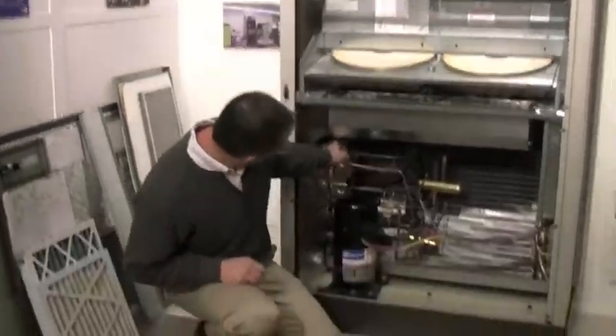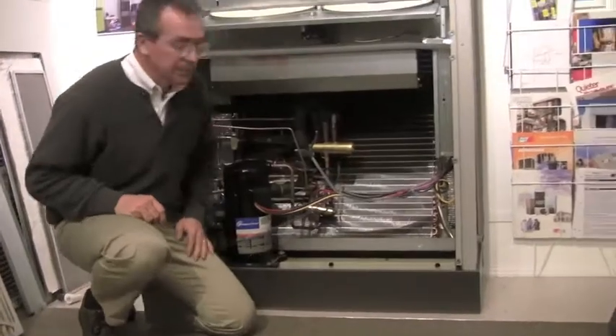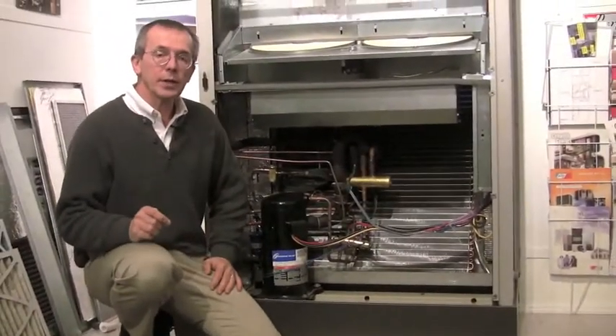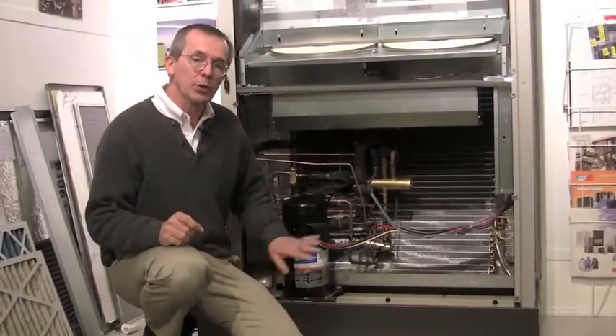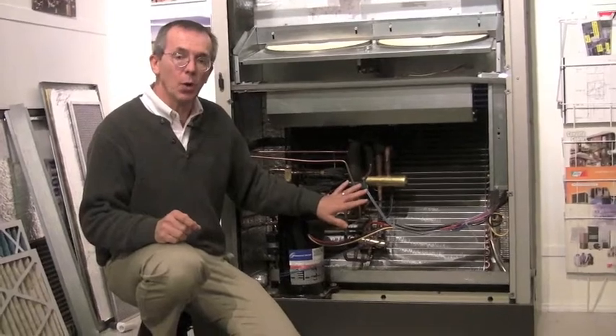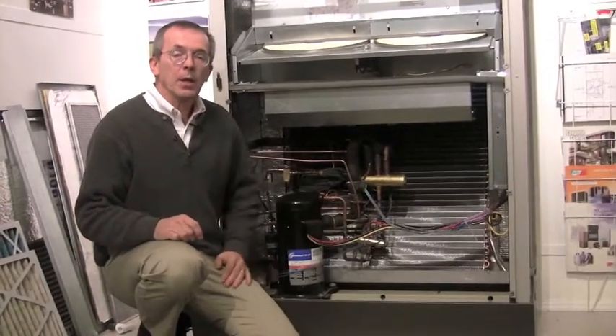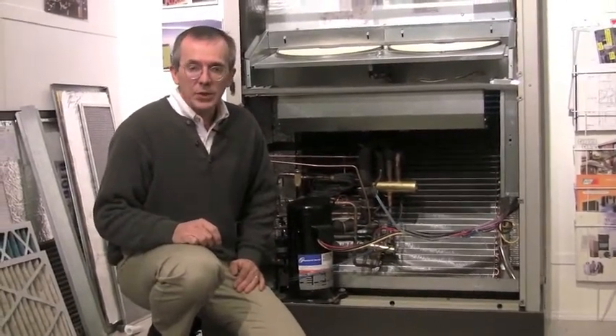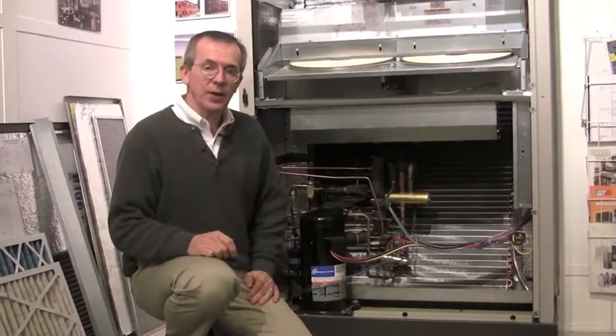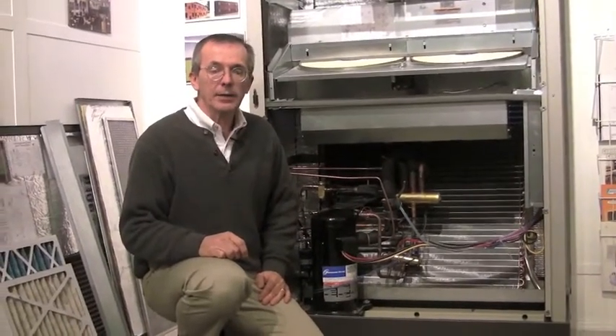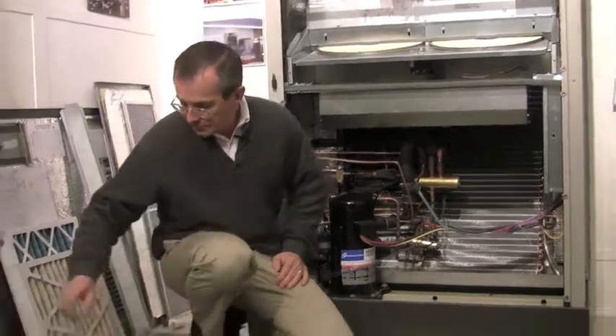The casters stay on the unit, and once the unit is rolled into place, those bolts protrude into the unit at this section and this section. Washers and nuts are applied to the bolt to draw the unit to the wall sleeve. The purpose of the 14 inches thick is because the condenser fan needs to slide back into the wall sleeve.